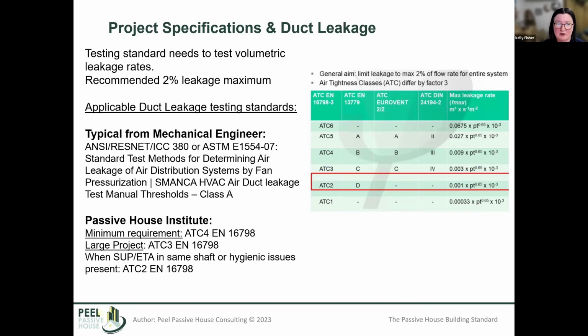There's a bit of a gap with leakage testing in the field when you're not using AeroSeal. How do you do your duct leakage testing? Having the proper specification, and the team that's going to be doing the testing understanding the testing criteria and how it all needs to come together, is very important. We find that on nearly every project we have to walk everybody through and hold some hands and make sure that we all understand what's happening and what needs to happen.